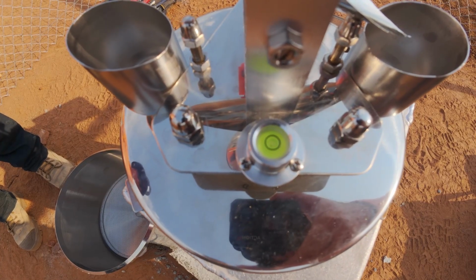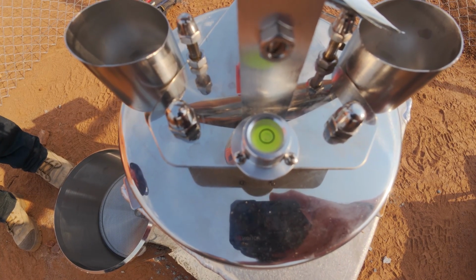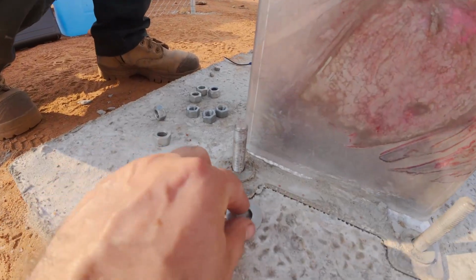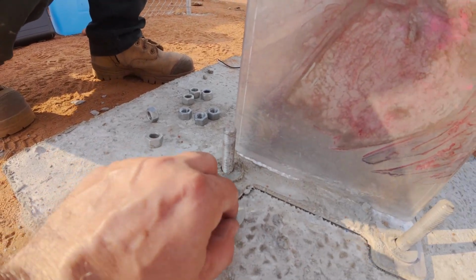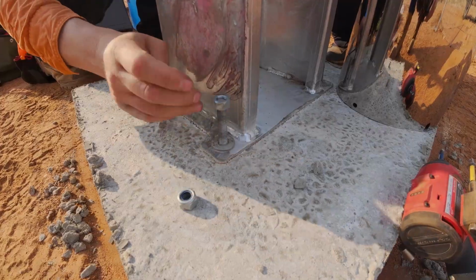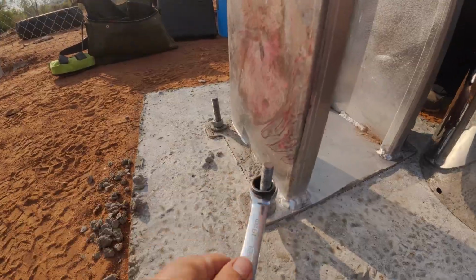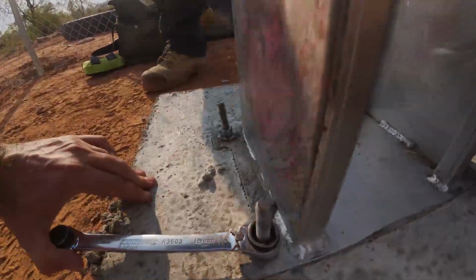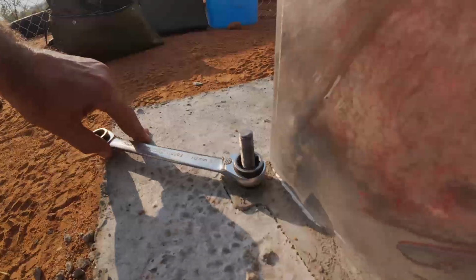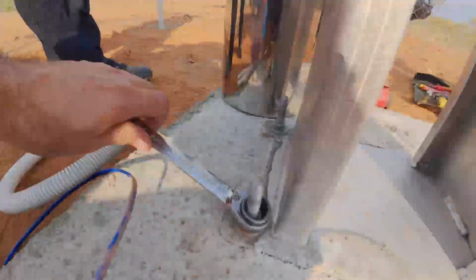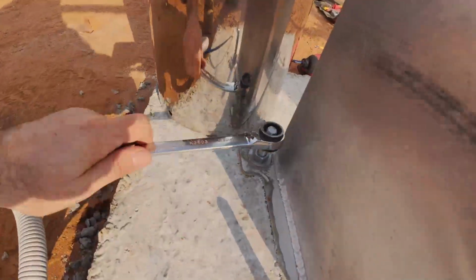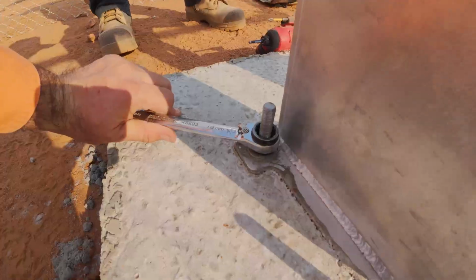Next, check that the spirit bubble indicator is level. If required, use spacers or washers added underneath the stand to level out the gauge. Once level, the nuts on the base of the stand can be tightened with a spanner. Be careful not to over-tighten nuts, especially if the concrete slab is not fully cured, as the bolts may pull through the slab and weaken the connection, requiring the use of a large drill and chemset anchors to repair any damages.